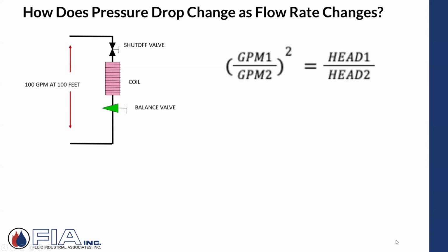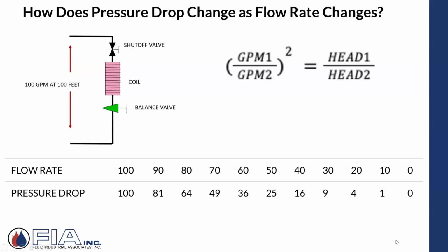Well, we've kind of talked about that already. That's that relationship between flow and head. You can actually figure out what the relationship is. As the flow reduces, the pressure drop reduces. That's that squared relationship. I don't have a calculator in front of me, but all we're saying here is whatever the percentage of flow rate is, if it's 100% flow, the pressure drop's 100%. If I reduce the flow in half, from 100 down to 50 gallons a minute, and I square it and multiply it by the original 100-foot pressure drop, it'd only be a quarter of that. It'd be 25%, or anywhere in between.